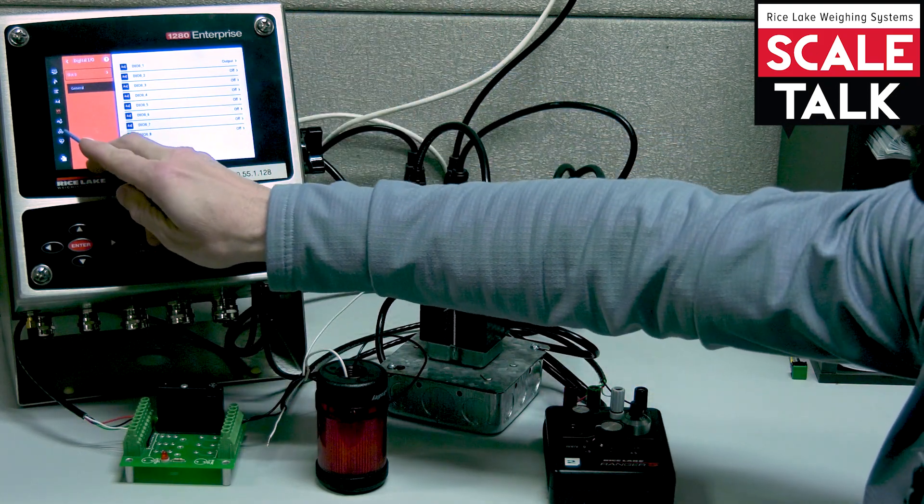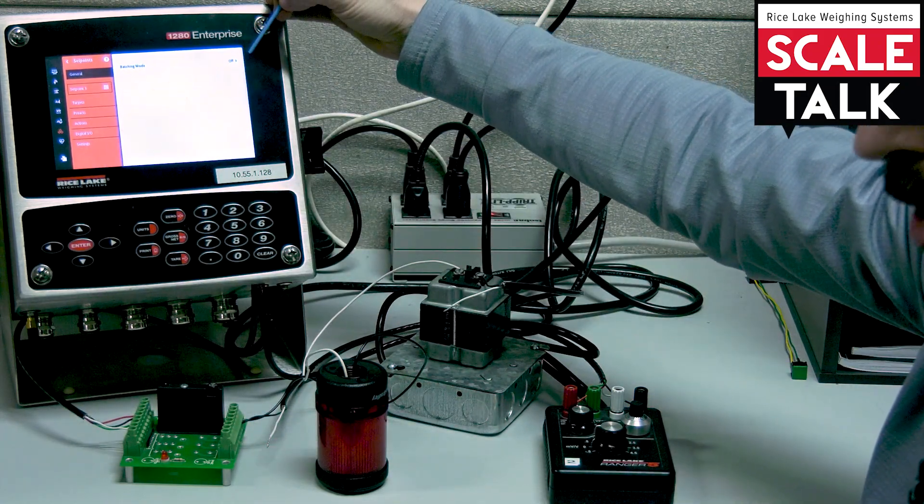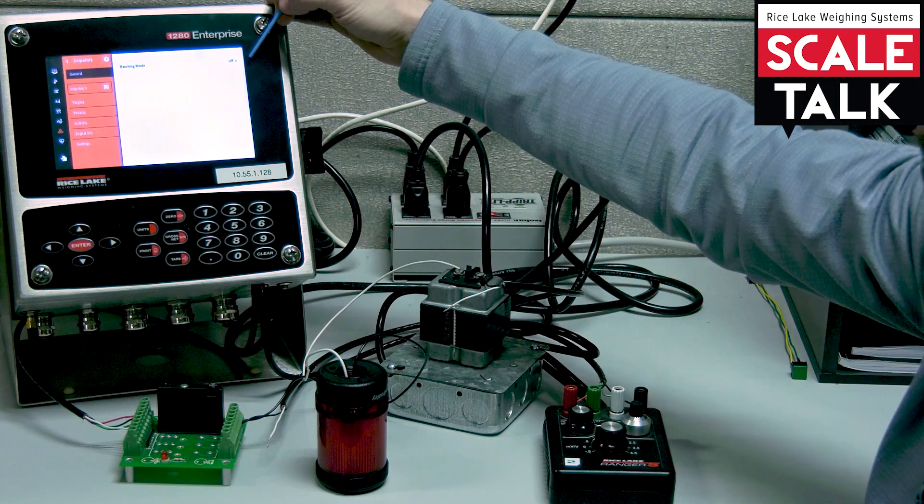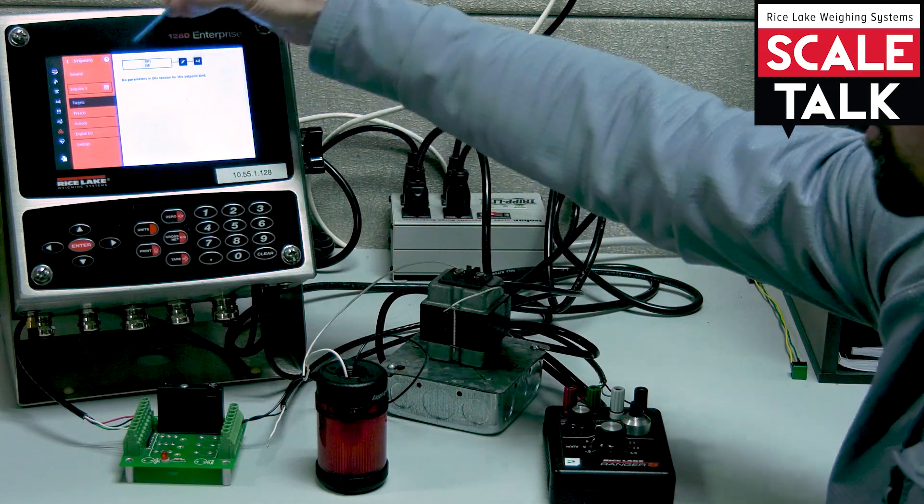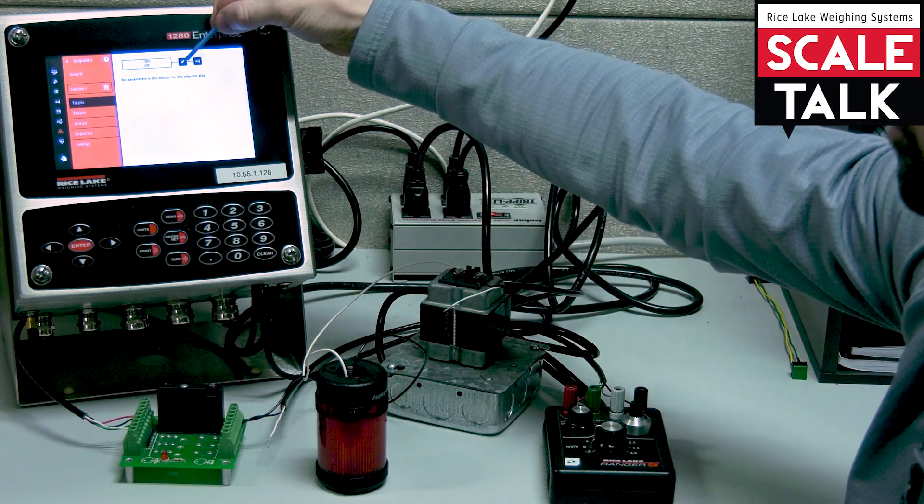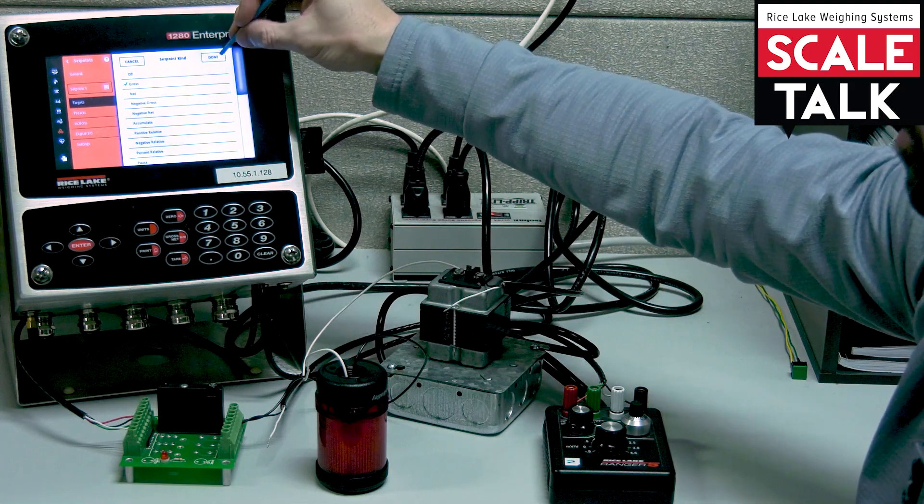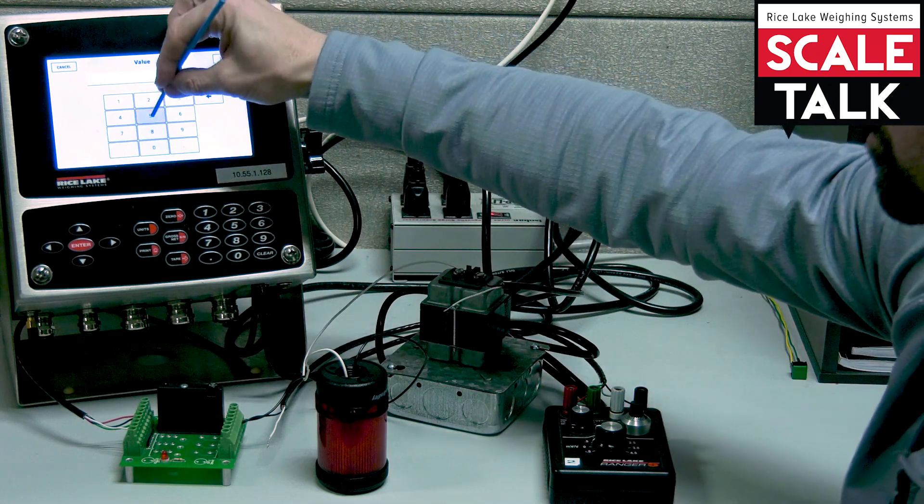I'm going to switch over to the set point menu now. Our batching mode is off because we're not going to use batching right now, just free running. Go into my set point one that's selected, go to the target. We see that's off. Hit the pencil. We'll select a simple gross set point. Hit done. I'm going to set the value for 500 pounds.